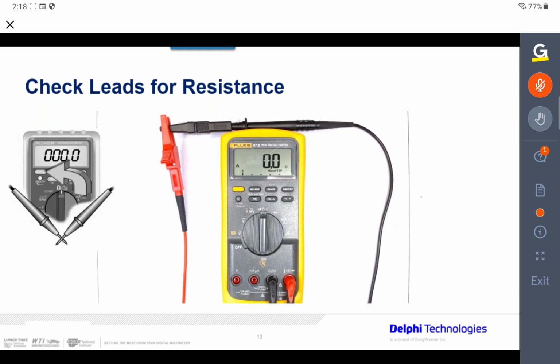So what it does, it erased the 0.2 or the 1.5, whatever it was. It erased it from the readings, but it's in memory somewhere. That means if you're having problems with the circuit and you're not getting quite the readings you want, you should have already zeroed your leads. Now, if your leads are within 0.1 to 0.2, your leads are good. If by some chance your leads are reading 0.3, 0.4 or more, the leads need to be replaced. And you should do this on a regular basis, especially when you start using your meter in a process.